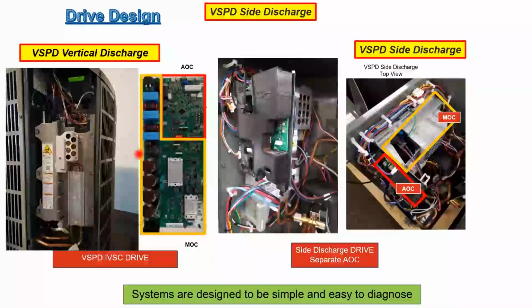There's our vertical discharge, one piece with the AOC on top. You can actually remove this and swing it out so you can access it. You can see the top AOC and MOC. This is all one unit that needs to be replaced if it's bad. Same with the drive.